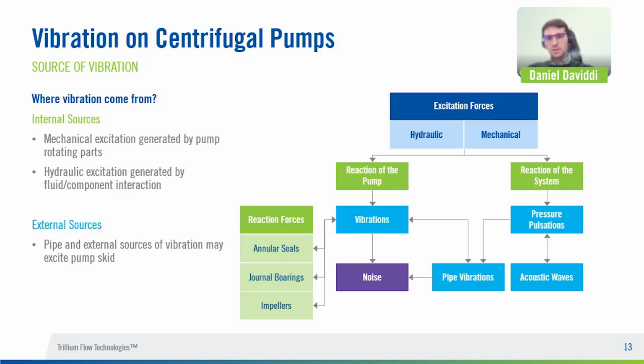Internal sources can be mechanical, originating from rotating components, or hydraulic, due to fluid-component interaction, for example fluid-impeller, fluid-journal bearing, or fluid-annular seal interaction. External sources are due to the interaction of the skid with, for example, the plant pipeline or nearby running machinery. But in any case, the combination of these complex sources results in a reaction of the pump and skid system, with vibration and noise that can exceed the system resonance frequency and act as a propagation medium for the previously described excitation. So the purpose of this slide is to highlight the complexity of the vibration issue, where causes and effects can often be combined.